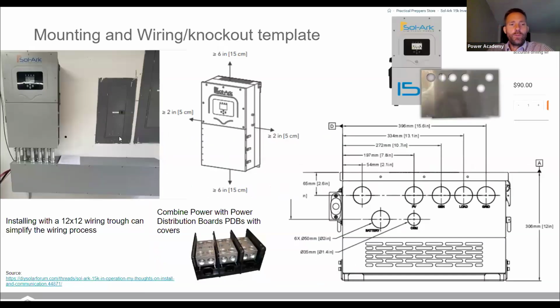You do need to have 6 inches of spacing between the gutter and the inverter that's above. That's a minimum. On the sides of the inverter, it's 2 inches, unless you've got another inverter directly next to it, and then it's 6 inches. So a real nice way to do the installation is with a wireway, and then you can put things like your power distribution blocks in there to do combining, etc. Or one of those Victron units would easily fit into one of these 12 by 12 wireways.